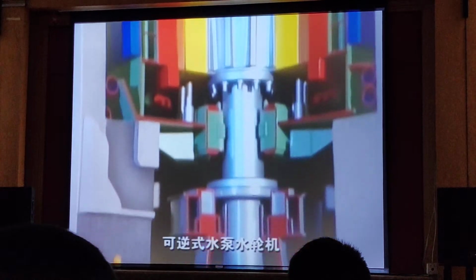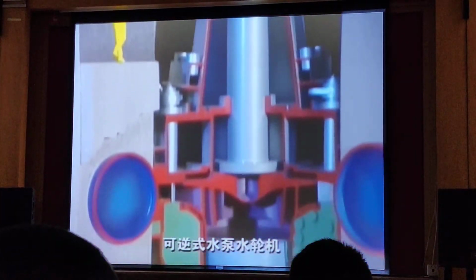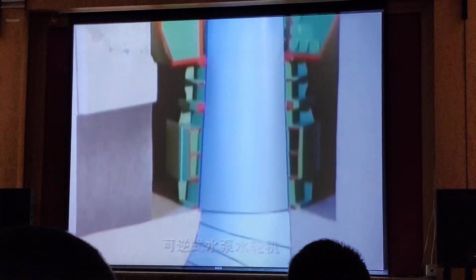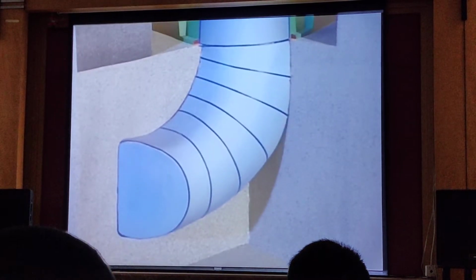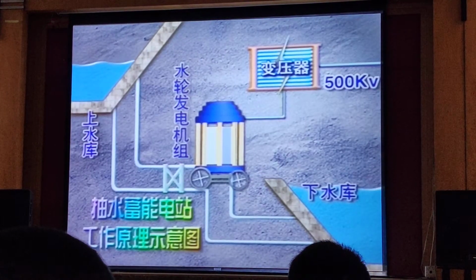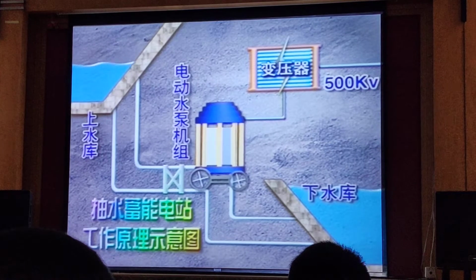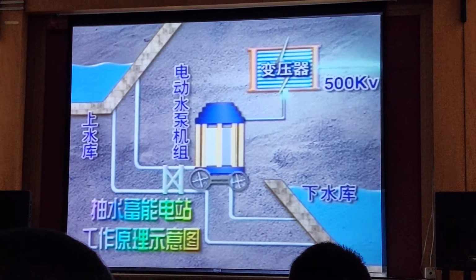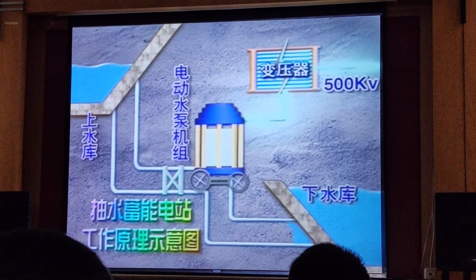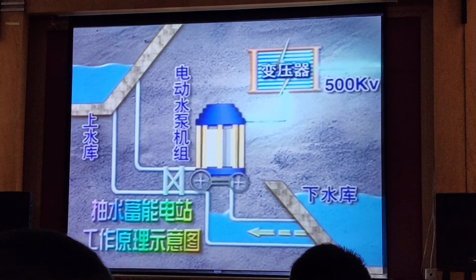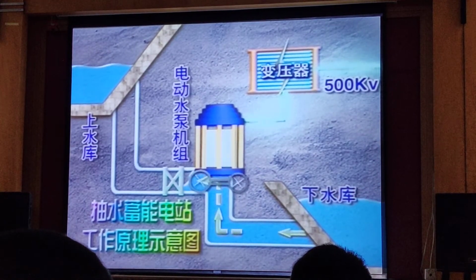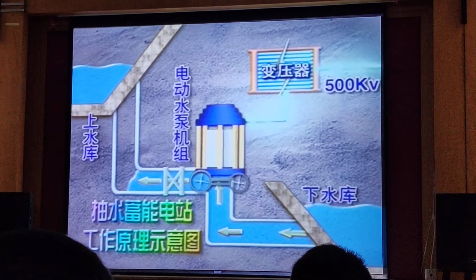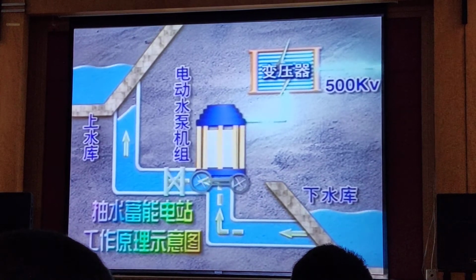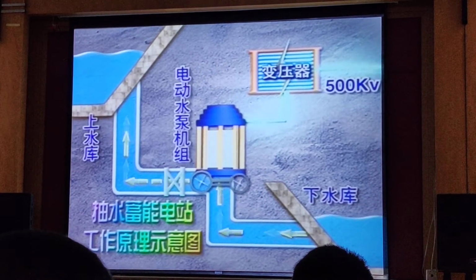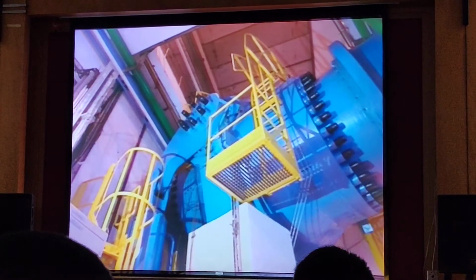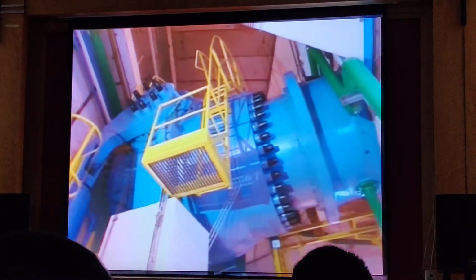The machine is of single stage, reversible, and Francis type. It runs clockwise as a turbine generator and counterclockwise as a pump motor. When the power system has surplus electricity, the redundant power is used to drive the unit as a pump motor. In this case, the water from the lower reservoir is pumped up into the upper reservoir for storage.